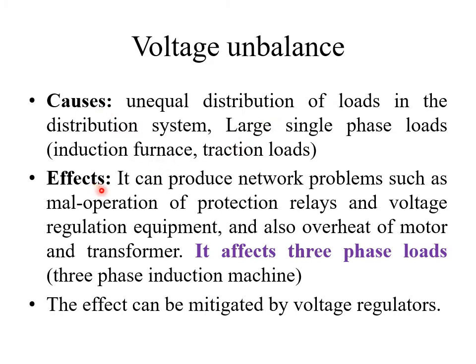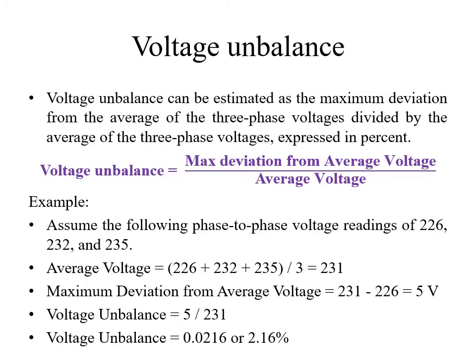The effects of voltage unbalance include network problems such as relay failures, effects on voltage regulation equipment, and heating losses in motoring loads. It particularly affects three-phase systems and three-phase loads. To avoid these effects, it is recommended to use voltage regulators. Voltage unbalance can be estimated by finding the average voltage, then calculating the maximum deviation from that average; their ratio gives the voltage unbalance.